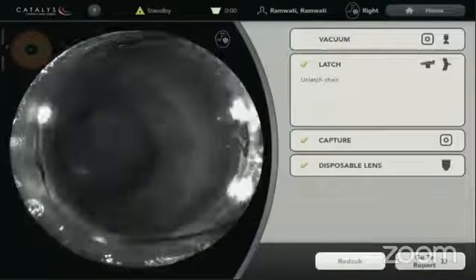The most important thing you told us — like that toric marking — is a new feature of this machine. Will the toric marking be radial? Yes, these are two radial marks. Will it have any effect on the refractive error? No, they are only intrastromal and they do not have any effect on the refractive error because these are not like an arc. They are in the periphery and will be alright.